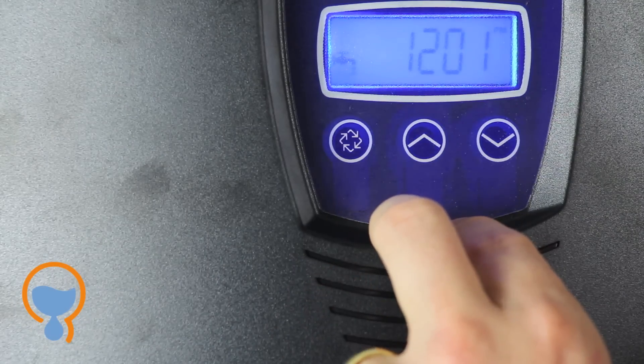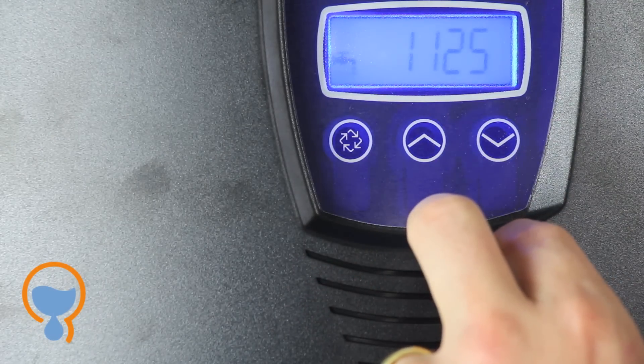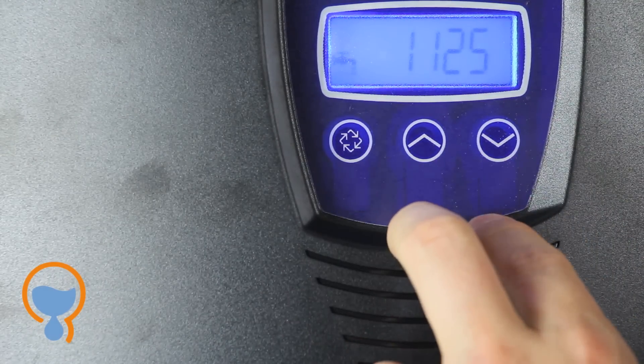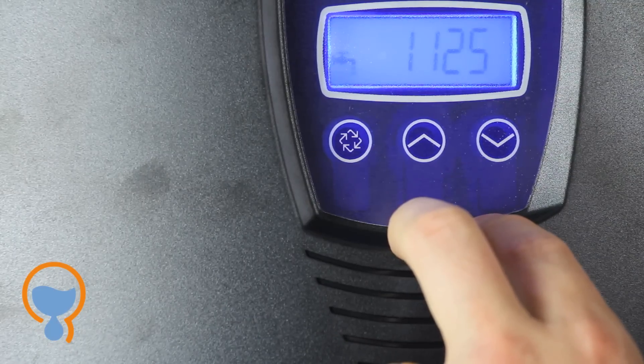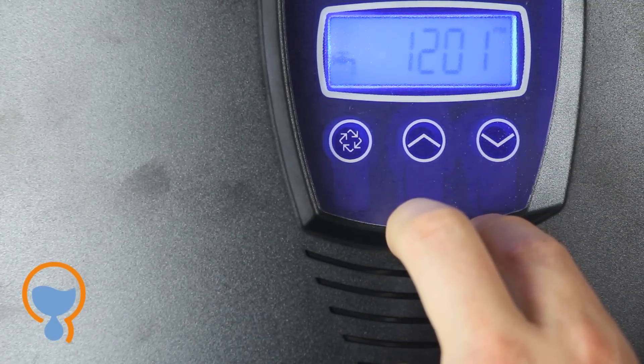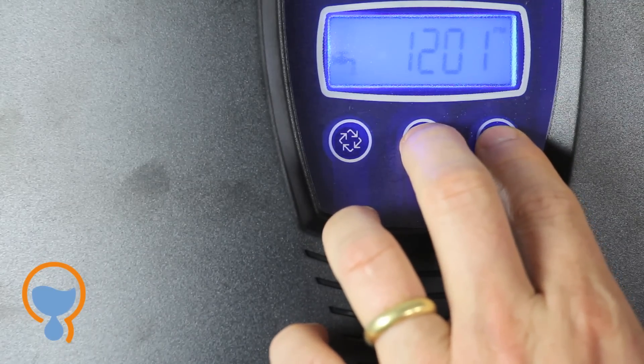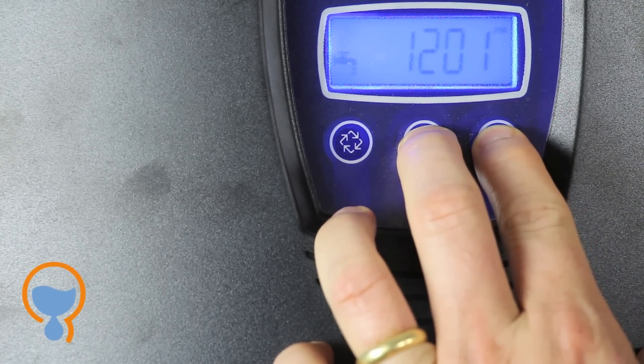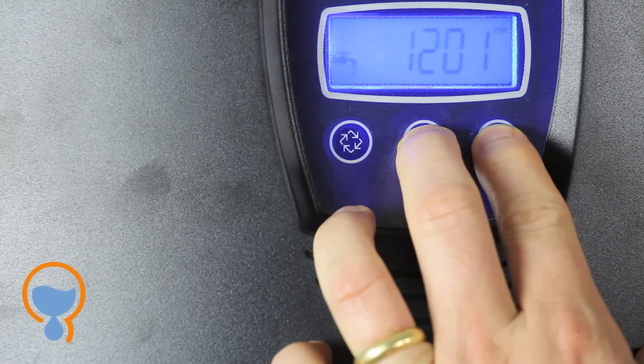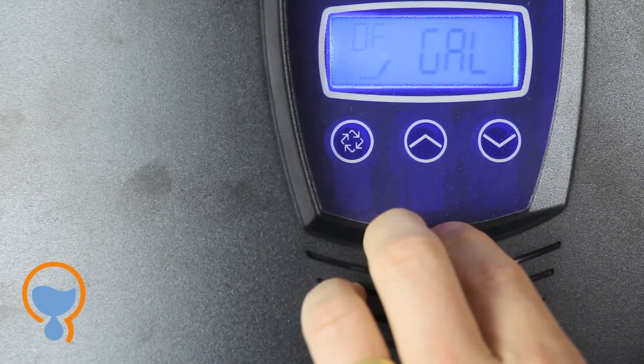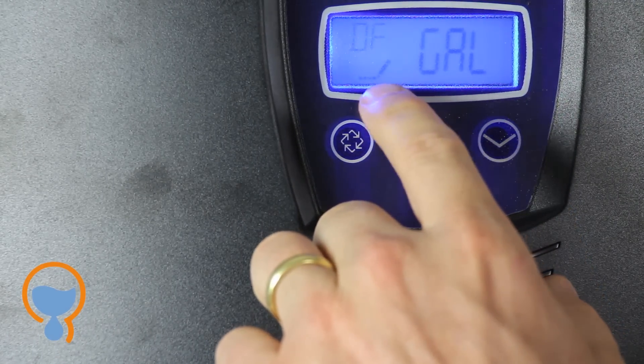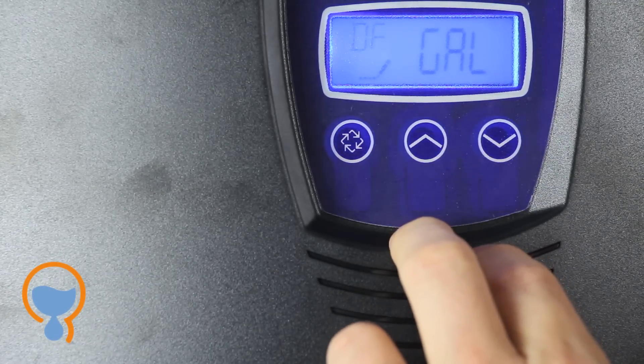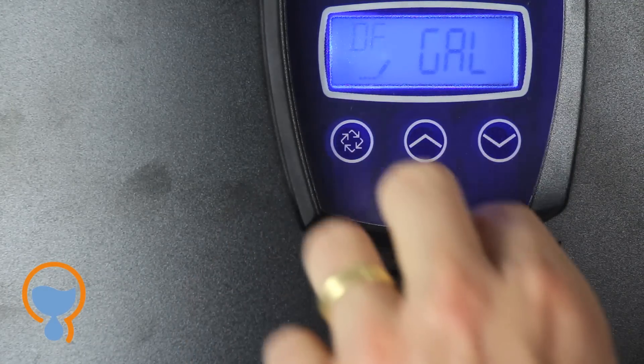Now the time is set at 12:01 PM and it flip flops between the time and the number of gallons remaining before the next regeneration. So we're going to press and hold the up and the down arrow at the same time and hold them down until we enter the programming mode. You know you're in the programming mode because you get this little pencil icon here and you get a code in the upper left hand corner.